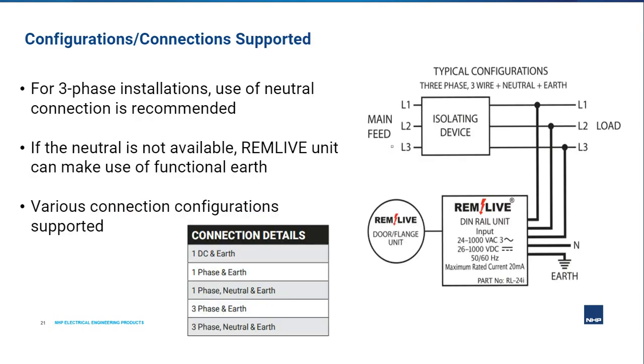Let's now look at how the REMLIVE unit is connected and the typical wiring configurations that it supports. As seen in the connection diagram, the REMLIVE unit's inputs are connected to the load side conductors of the isolating device to monitor the voltage levels in that 24 to 1000 volt AC and 26 to 1000 volt DC band. Therefore, when it detects voltage in that range, it illuminates the LEDs on the display unit to warn the operator of the presence of live voltage.